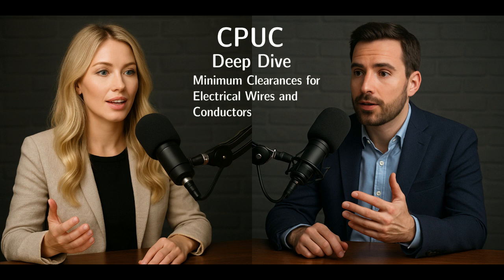So this separation between different types of utilities, you mentioned it can be dramatic. Oh, yeah. Take communication conductors, like your phone or internet line. They need 24 inches of clearance between them and something called span wires. Span wires, what are those exactly? They're basically support wires, often holding up heavier cables or equipment, not energized usually. Okay, so 24 inches, 2 feet from a support wire. Right. But that same communication line needs 48 inches, 4 feet of clearance from a standard 0-750 volt supply conductor. Double the distance just for basic power.